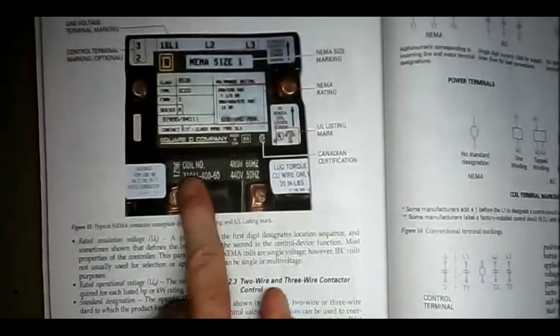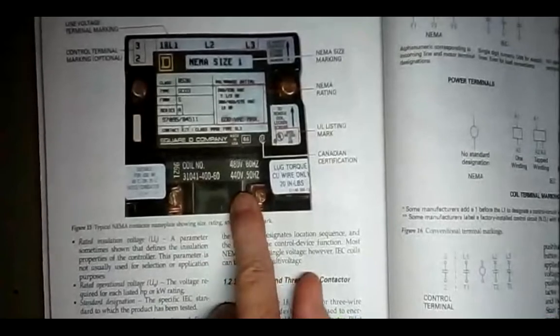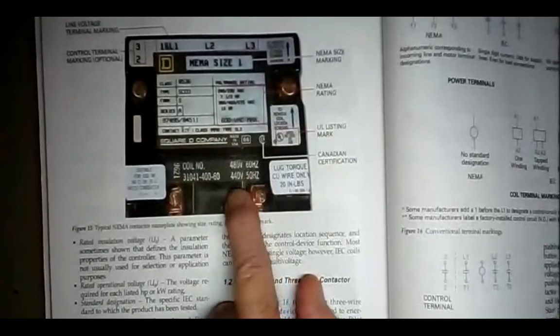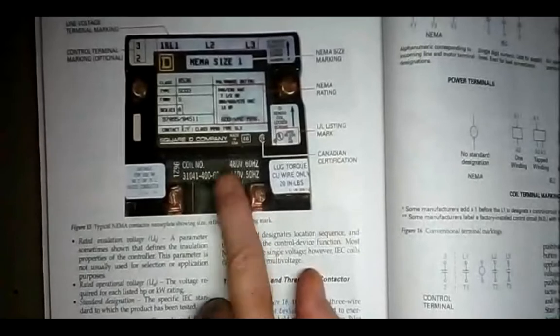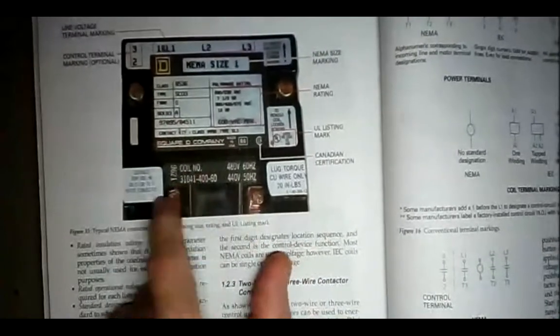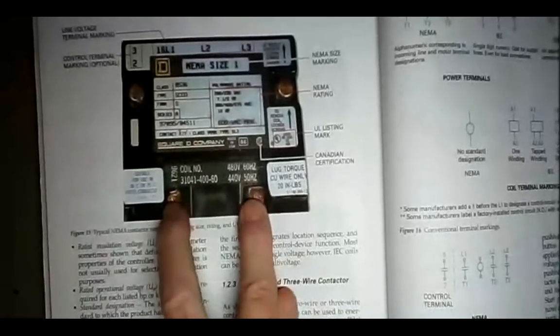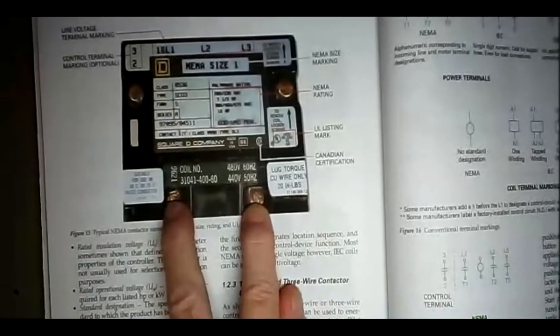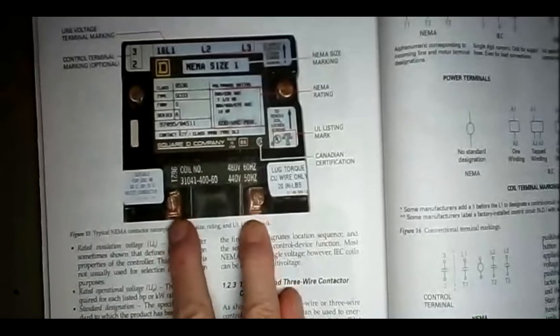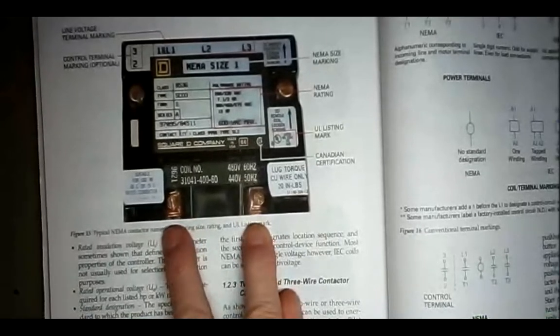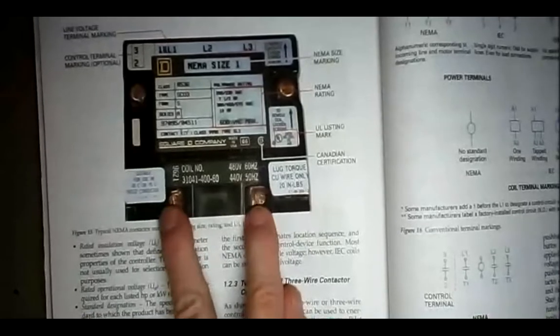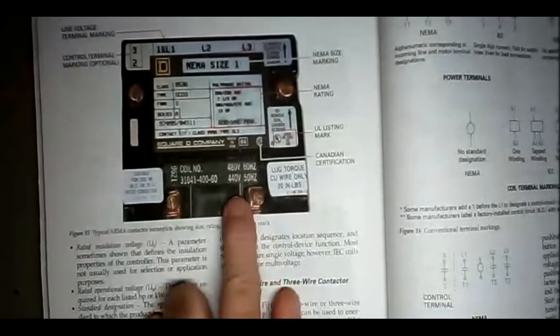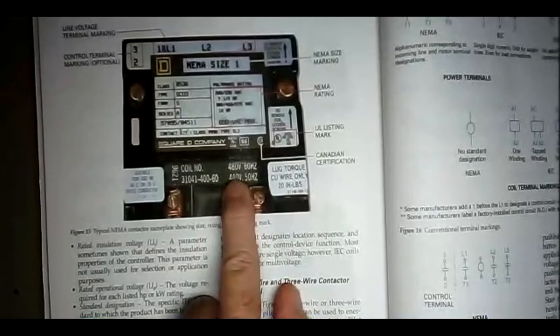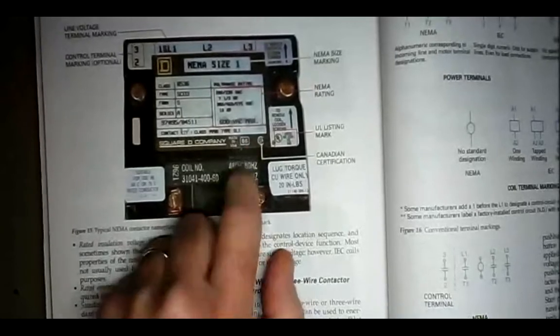Here it tells us that the coil is 440 to 480 volts. They're telling us this is a 480 volt coil. So we'd take line 1 and line 2 and hook it up across this coil in order to make it work. We could go through push buttons and start, stop, what have you, come back to this and feed this with 480. We would rather see this saying 120 because 120 is a lot safer.